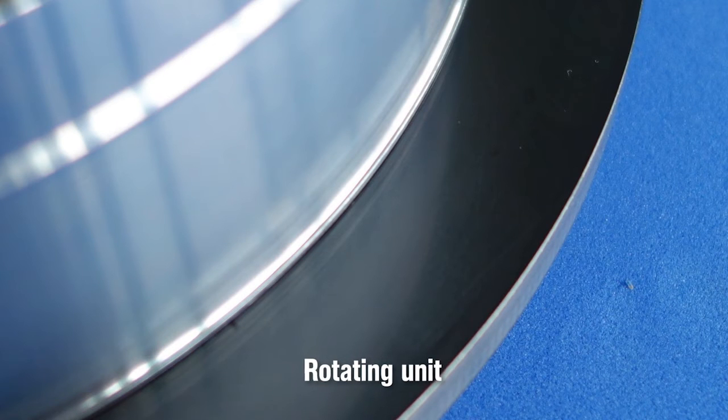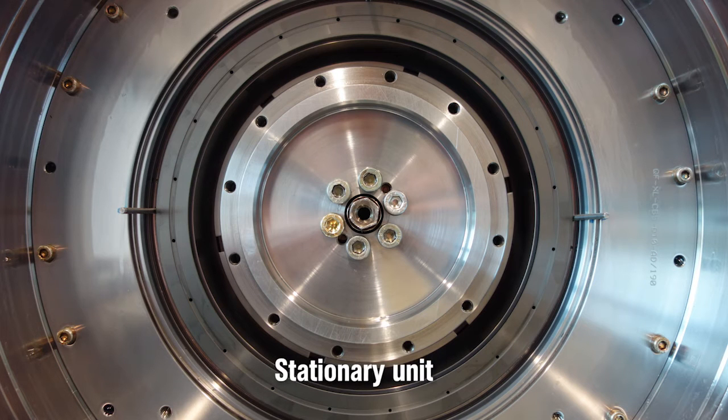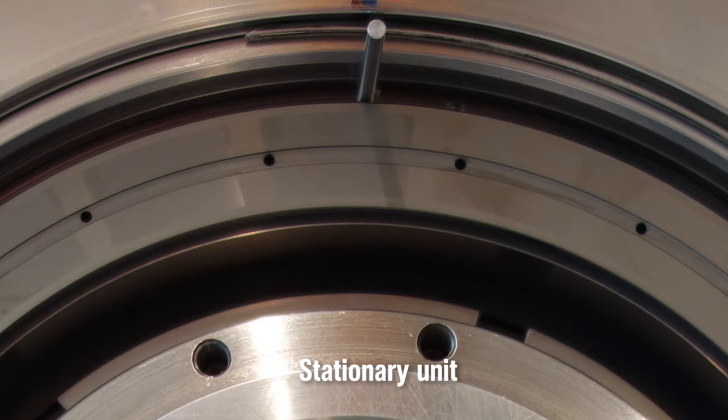The COBA seal is reliably oil-tight. The stationary unit is in perfect condition. There are no traces of oil on or between the contact surfaces of the seal.